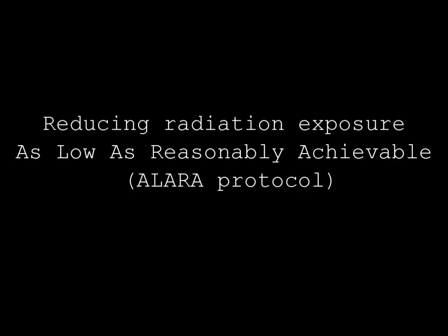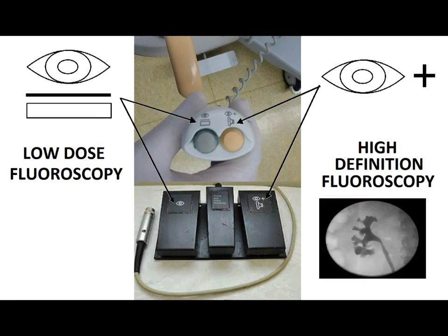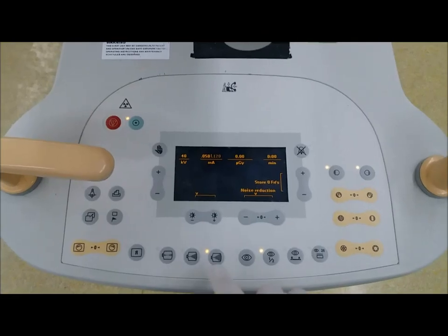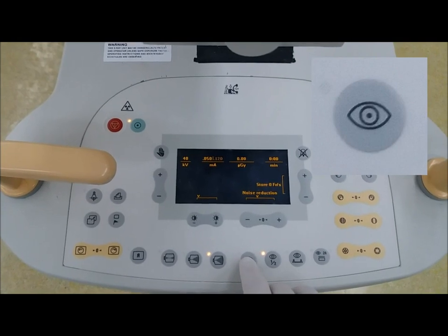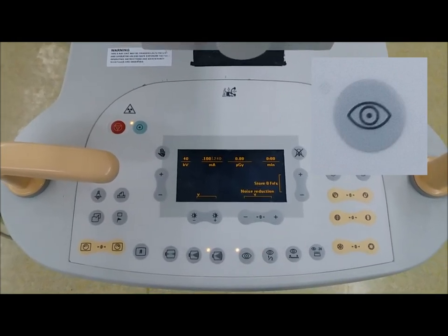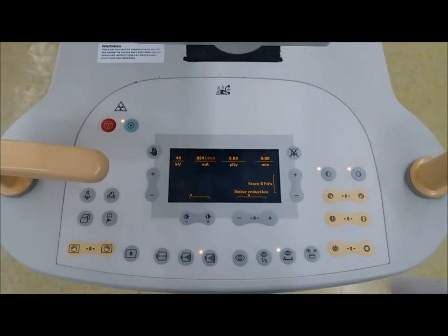Reducing radiation exposure for patients and medical personnel: use high-definition fluoroscopy to initially depict collecting system anatomy and its relation to stones, and low-dose fluoroscopy should be employed to monitor C-arm repositioning, puncture, and dilation maneuvers. Continuous fluoroscopy produces high quality static or dynamic images in both high-definition and low-dose fluoroscopy modes. To further reduce radiation exposure, real pulse fluoroscopy can be used.